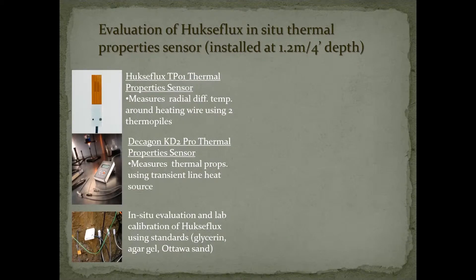In addition to looking at the soil moisture and the temperature gradients, we installed Hukseflux thermal property sensors that are designed to be left in the ground and give you continuous measurements. This is the first time that I know of that anyone has used this sensor and installed them at depth for the purpose of getting thermal properties for ground source heat pump applications. The sensor gives you not only thermal conductivity but also thermal diffusivity.